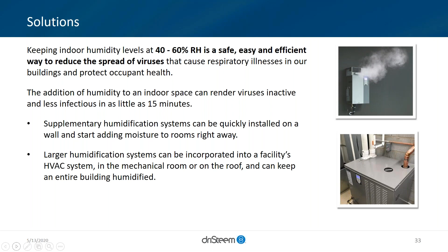We'd recommend any strategy start with a site survey. Most healthcare facilities in the US were commissioned with humidification, but this equipment may not be operating due to maintenance issues, may have been turned off, or humidification levels reduced. Taking RH readings using a hygrometer, or checking levels via the building management system in areas that may experience COVID cases or where asymptomatic cases may present, will quickly determine if a facility is optimizing its defense against the COVID virus. A target of 45% RH is generally recognized as providing positive benefits.